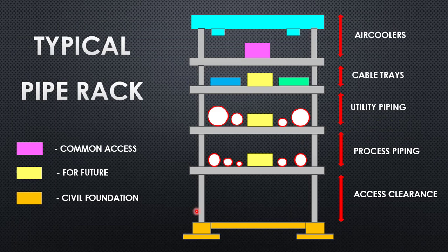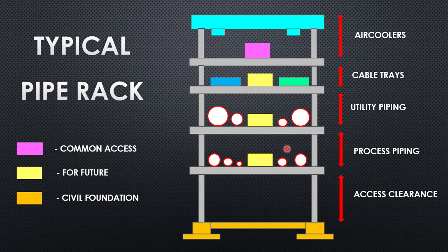Now we'll see the typical structure of a pipe rack, which is very important to understand. The first level is known as the access level, designed so that small vehicles like forklifts and small cranes can enter below the rack to carry out maintenance activities comfortably. The second level is for process piping, which is laid at this level to reduce the length of the piping and keep process flow efficient. The next level is for utilities such as steam, condensate, water, and air, which are planned above the process piping.